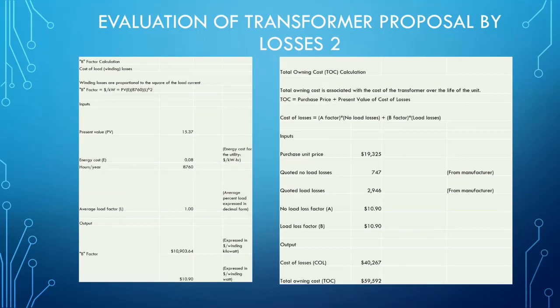The next thing they're going to do is evaluate the winding losses. And they're going to figure out, how am I going to load that transformer? How am I going to load this transformer to 100%? Or is it going to only be loaded to 50%? And we call that the loading factor. And that's going to help them take the cost of those losses and discount them back to present value.